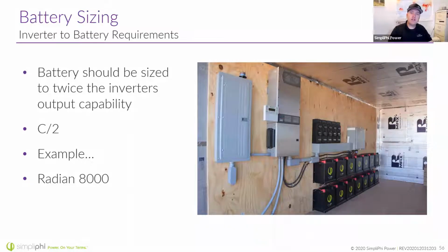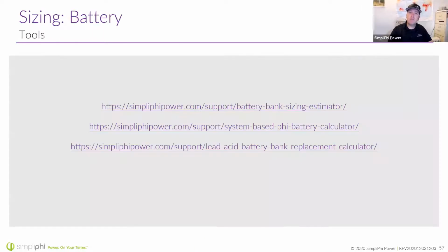So the two concepts there: we're sizing for energy and we're sizing for power. You don't have to remember any of that, because we have calculators online. This first calculator is simple battery bank sizing: days of autonomy, depth of discharge, your consumption. The second link is a little more in depth. It starts asking you for pieces of equipment, to make sure they are compatible. The last calculator, I'm not going to go through these. You can click on them yourself.